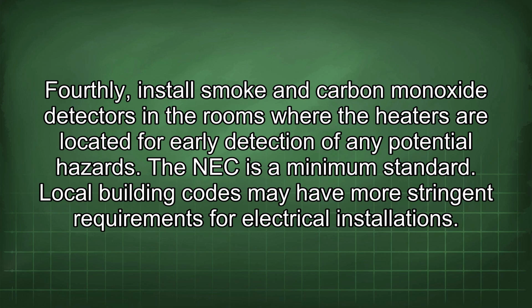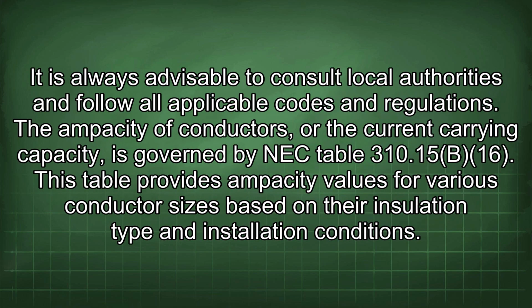potential hazards. The NEC is a minimum standard. Local building codes may have more stringent requirements for electrical installations. It is always advisable to consult local authorities and follow all applicable codes and regulations. The ampacity of conductors, or the current carrying capacity, is governed by NEC Table 310.15(B)(16). This table provides ampacity values for various conductor sizes based on their insulation type and installation conditions.